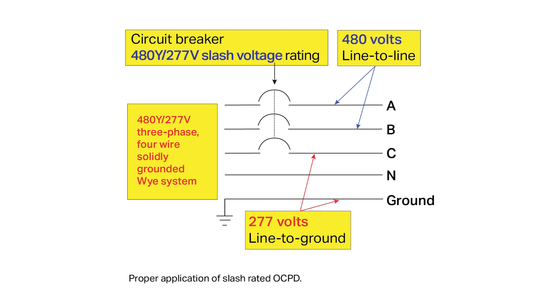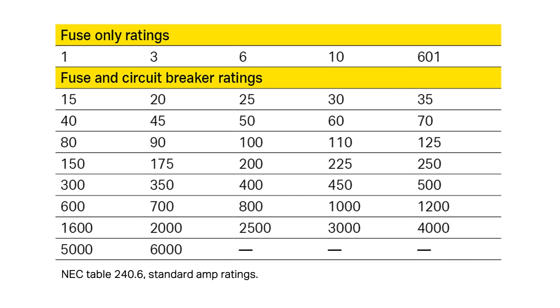The amp rating of the overcurrent protective device indicates the amount of current that can flow through the device without causing it to open. In many cases, the fuses are sized per NEC requirements, and the next standard size must be used per NEC section 240.6. In selecting the amp rating, consideration must be given to the load type and code requirements. The fuse amp rating normally should not exceed the circuit's conductor current carrying capacity that's determined by ampacity adjustment factors covering how and where it's routed or other NEC-related areas.